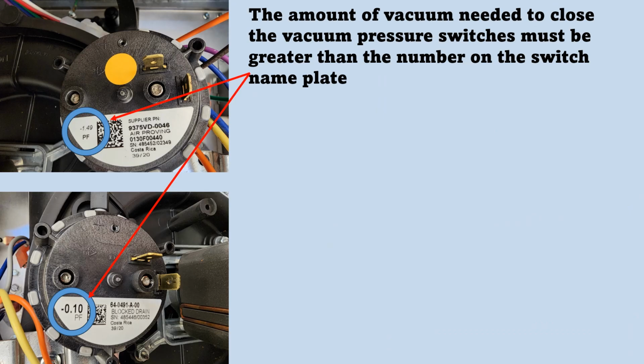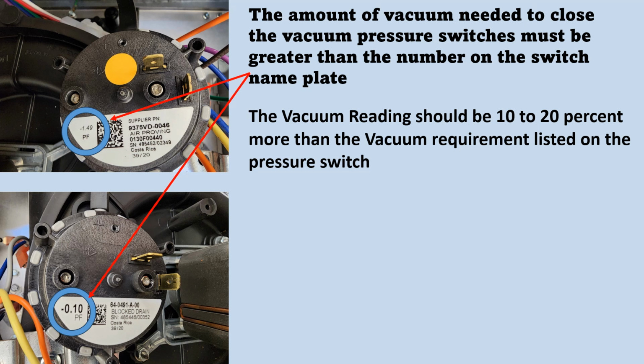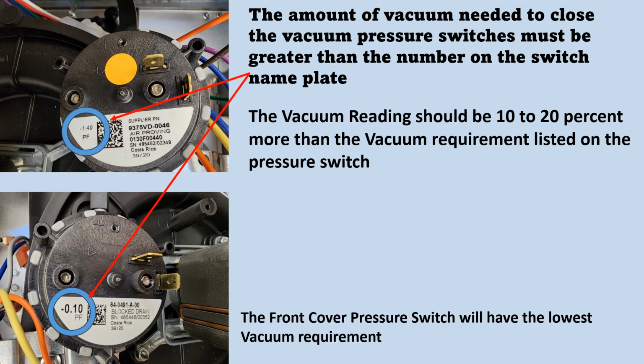The amount of vacuum needed to close the vacuum pressure switches must be greater than the number on the switch nameplate. The vacuum reading should be 10 to 20% more than the vacuum requirement listed on the pressure switch. And some can be even a lot more, but you should have at least 10 to 20%. The front cover pressure switch will have the lowest vacuum requirement, and usually that's on Goodman and Amana equipment, it's a negative 0.10.